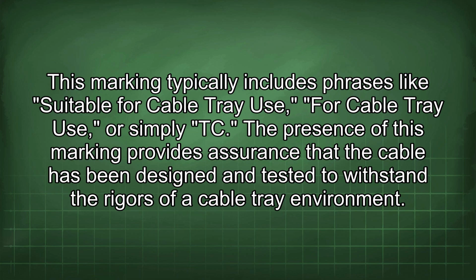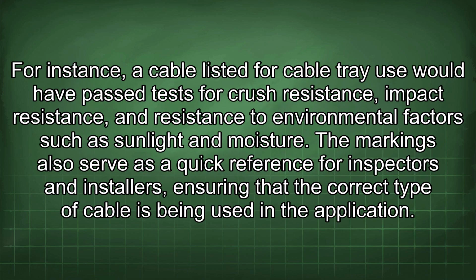The presence of this marking provides assurance that the cable has been designed and tested to withstand the rigors of a cable tray environment. For instance, a cable listed for cable tray use would have passed tests for crush resistance, impact resistance, and resistance to environmental factors such as sunlight and moisture. The markings also serve as a quick reference for inspectors and installers, ensuring that the correct type of cable is being used in the application.